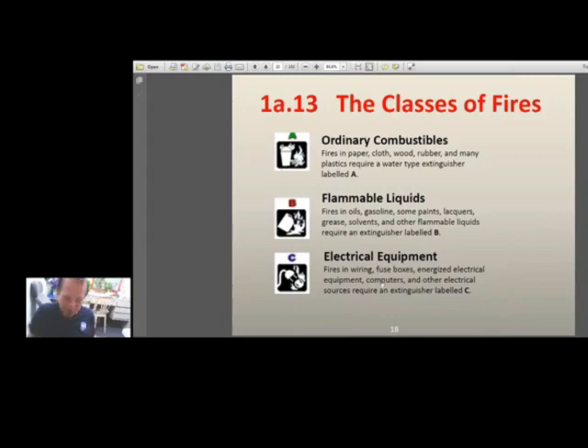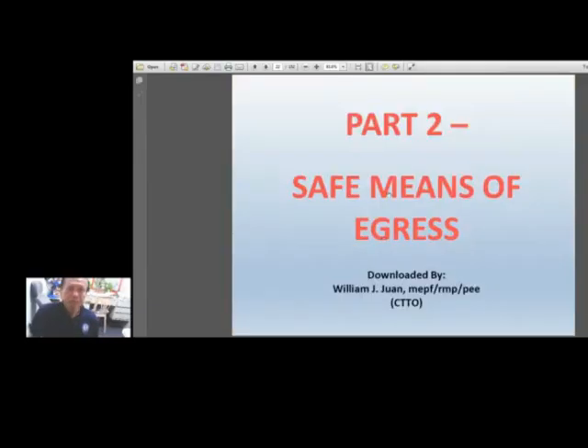So when you have arc flash, when you have electricity that would jump from one line to the other, like a short circuit, then that is class C fire. And for class C fire, you do not use water. For both type B and type C, you use extinguishing agents, for example nitrogen can be used there. Argonite is also possible, and of course some special materials like FM200, Novec, Inergen, and some other inert gases. Okay, so now we go to part 2.